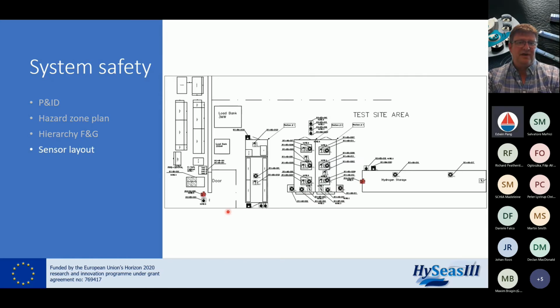Then we have the sensor layout. For the hydrogen storage we have two gas sensors and one flame detector for fire. Outside the container we have an emergency shutdown button that you can push to shut down the hydrogen storage.